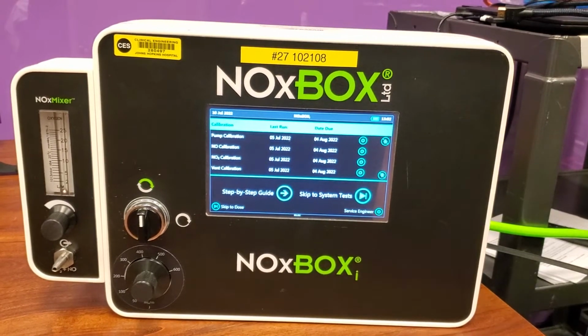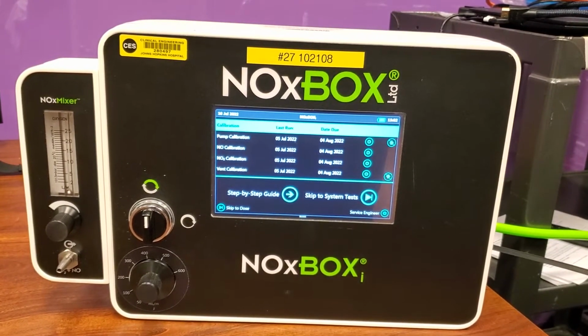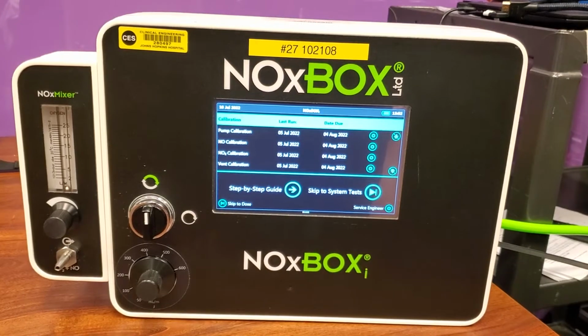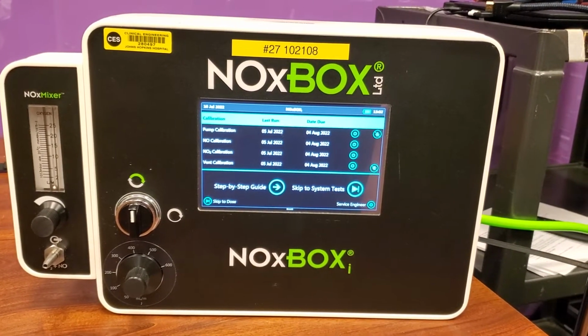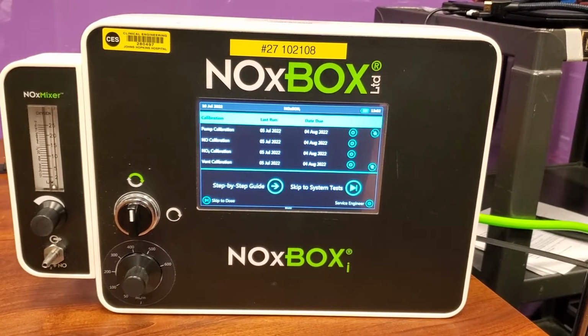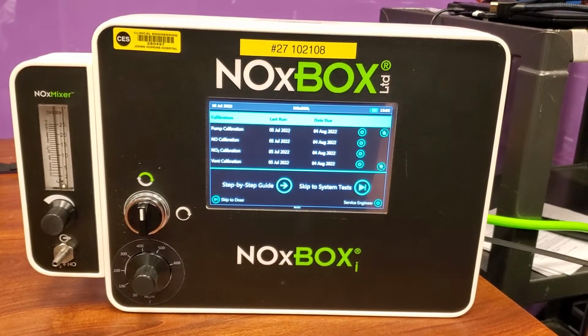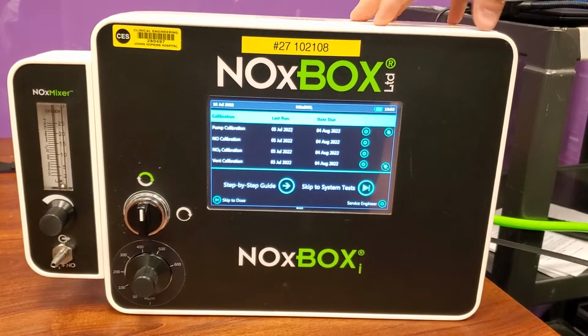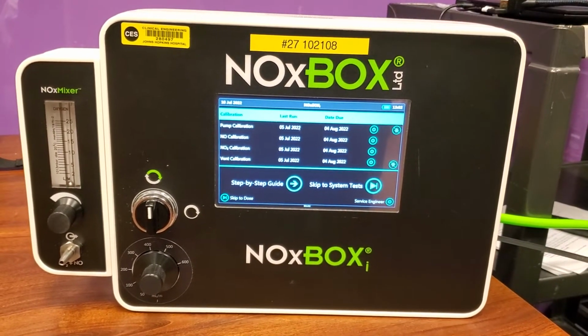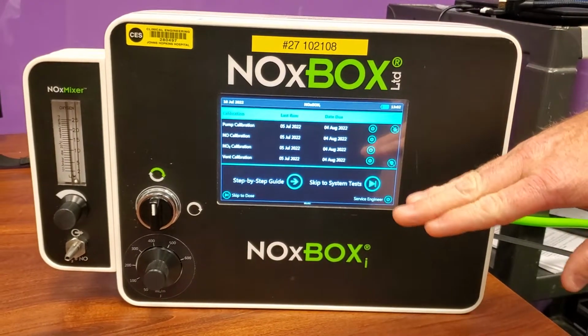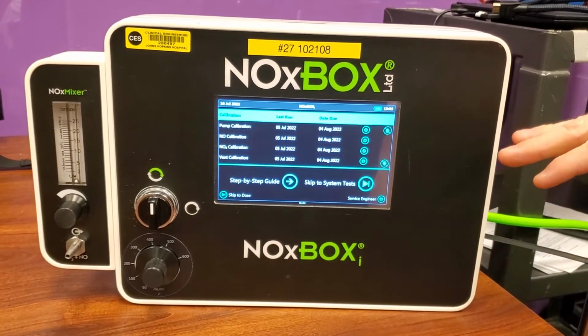If that is something that needs to be calibrated, that has to be done by respiratory. So you'd have to put this piece of equipment out of service, let SOC and clinical lead know, and use the backup machine. Once you start to feel comfortable with this machine, if you understand all the connections and the hookups, you can just skip to the system test and you're ready to roll. It'll just check the machine.